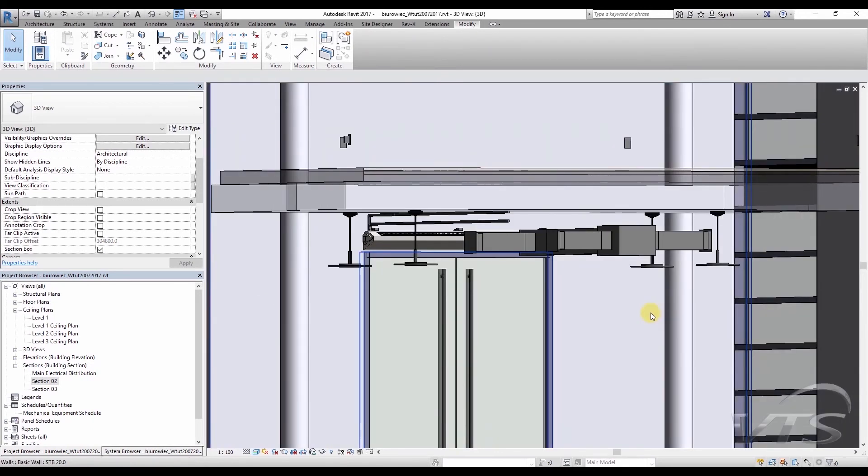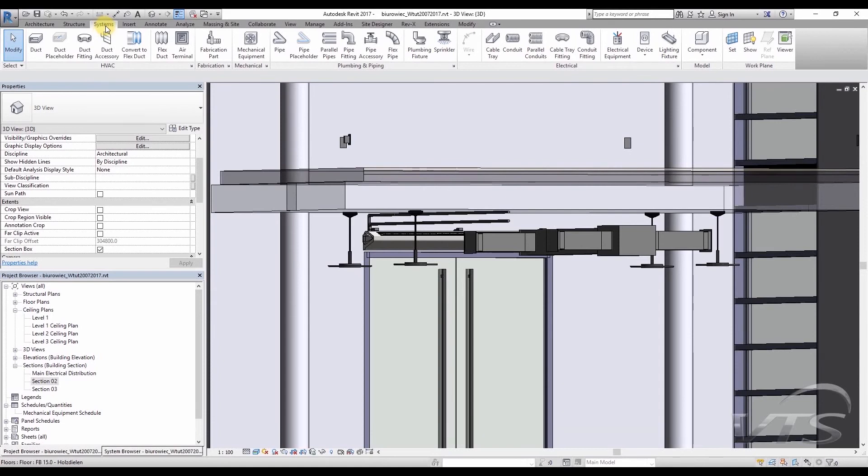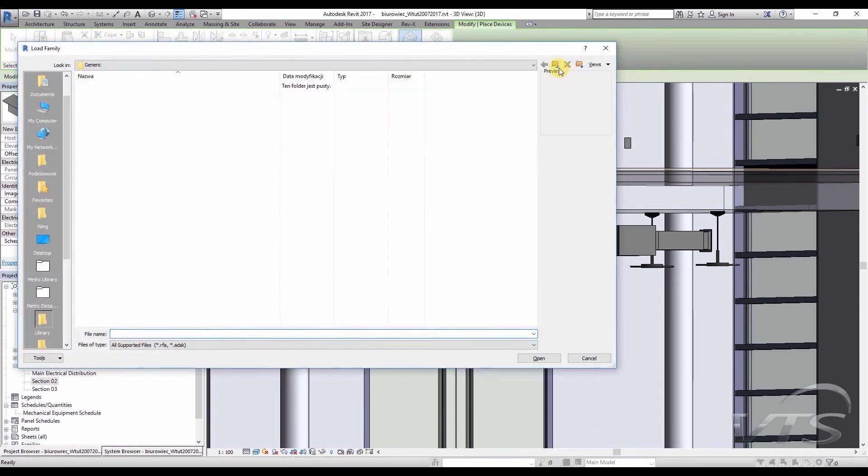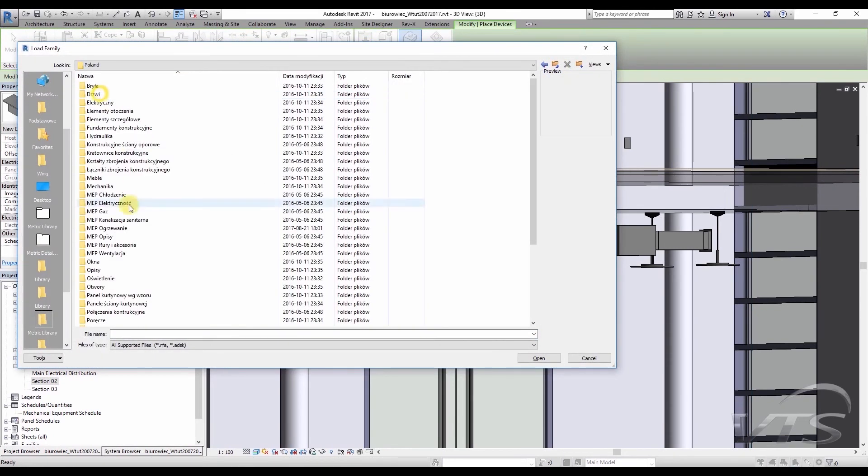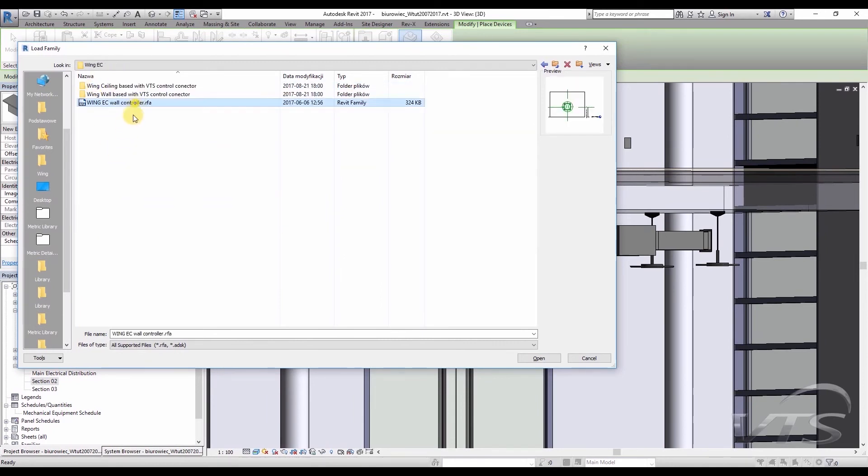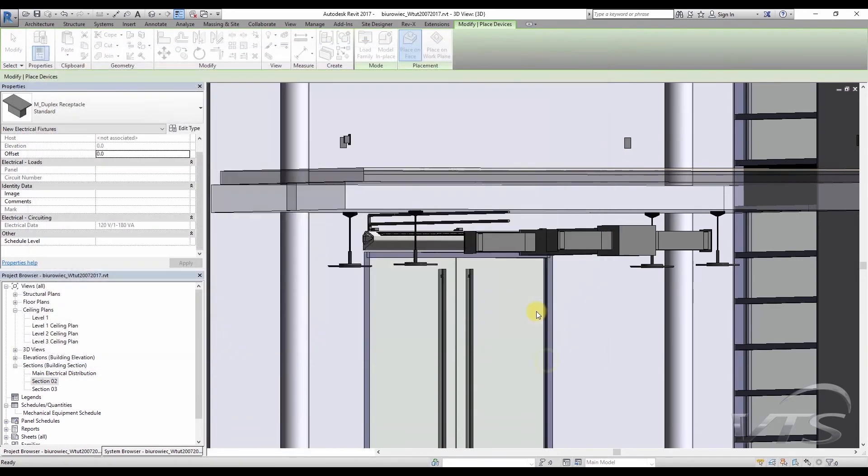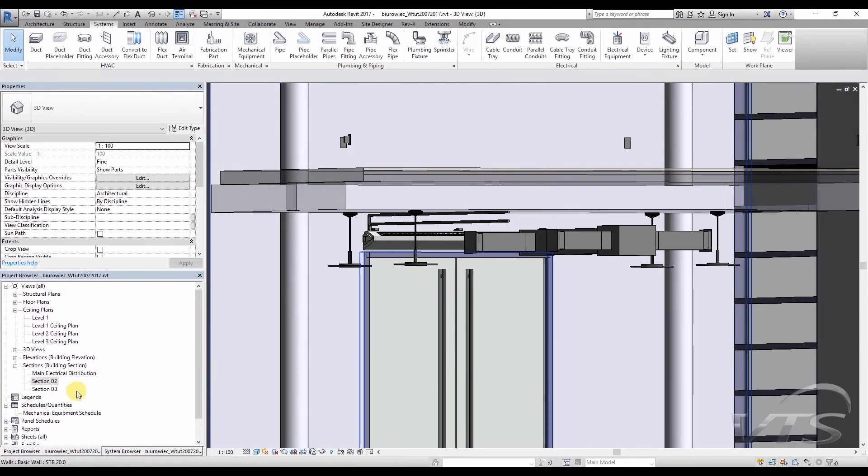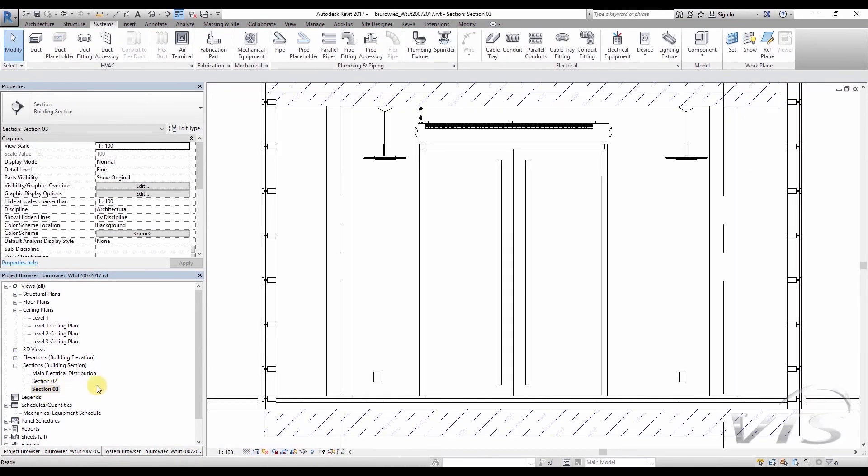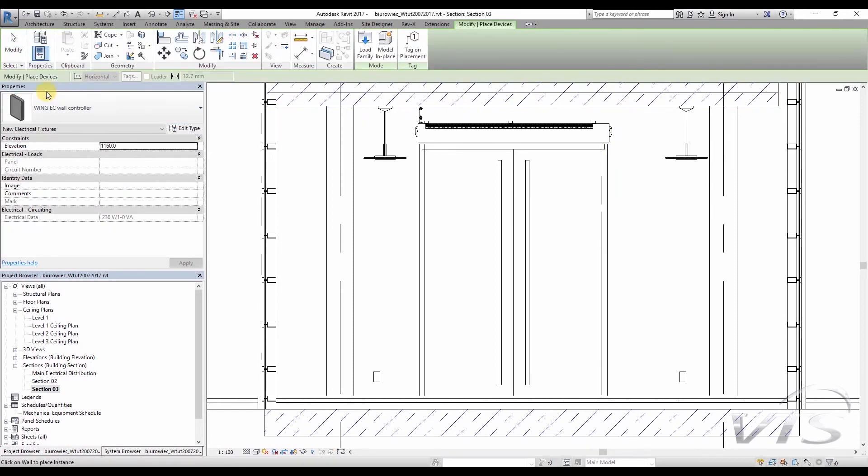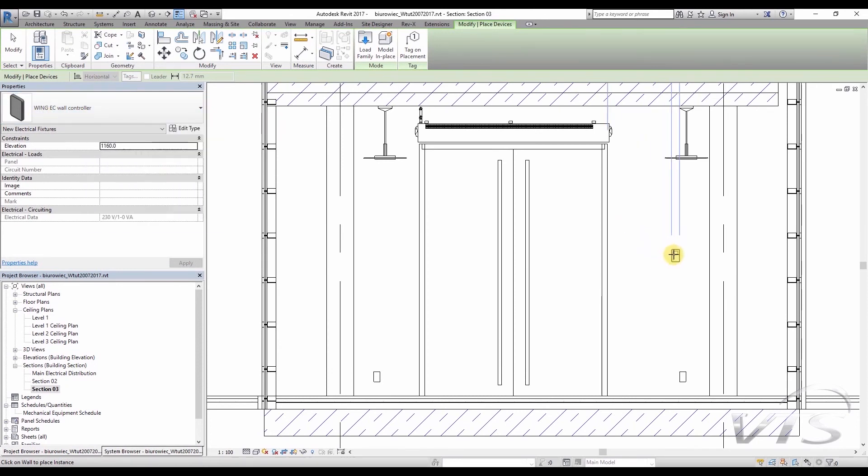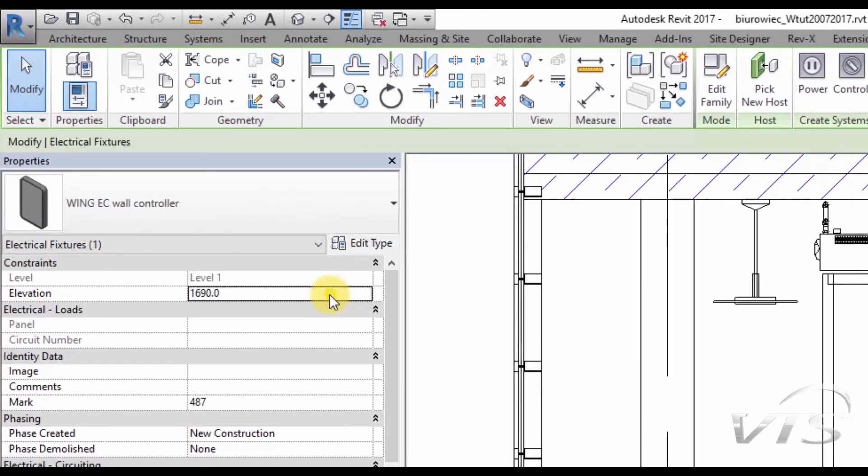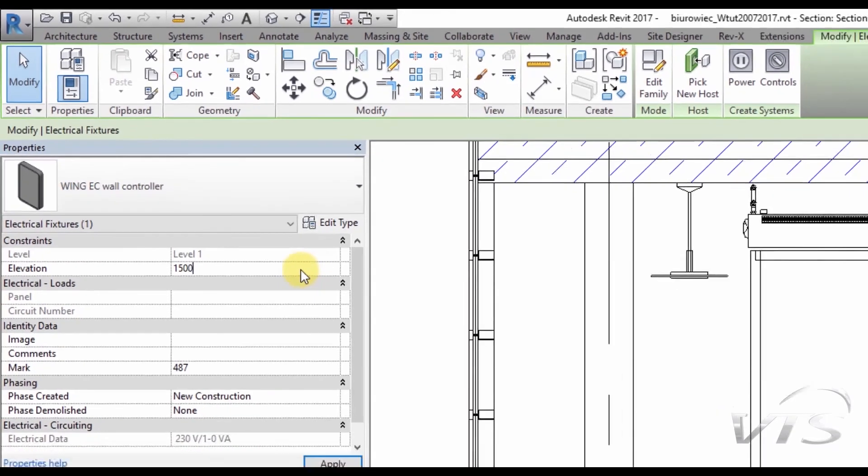A dedicated family has been created for the controllers, which we shall upload to the project in a while. So, we go to the Systems tab, after which we choose Device, Electrical Fixture, Load Family, and we navigate to the appropriate folder to which we have uploaded and extracted all families. Later, we choose the position Wing EC Wall Controller, and we click Open. At this moment, the controller has been uploaded to the project. Let's move the Section 03 view in order to be able to see the wall parallel to the screen. Then we choose Device and Electrical Fixture from the Systems tab. We make sure that the appropriate family has been selected in the Properties palette, and we insert the controller into the wall at the height of at least 1.5 meters from the finished floor level. I click with the left mouse button, and then I pick the controller, and I modify the elevation to 1.5 meters.